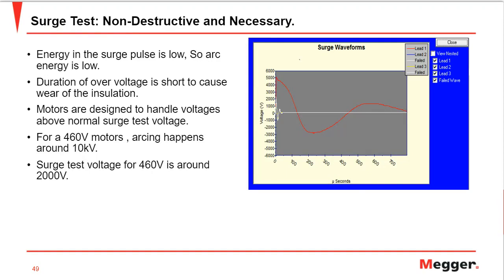Also, the energy which we use in surge testing is low, so the arc energy is low. For a 460 volt motor, even the arcing happens around 10 kV, and for a 460 volt motor, the surge test is conducted around 2000 volts. So whether we are aware of it or not, we hipot and surge test our motor more frequently than we realize in regular day-to-day operations.